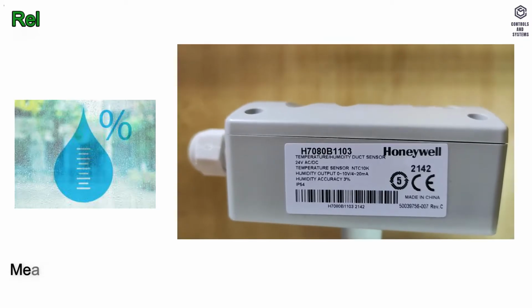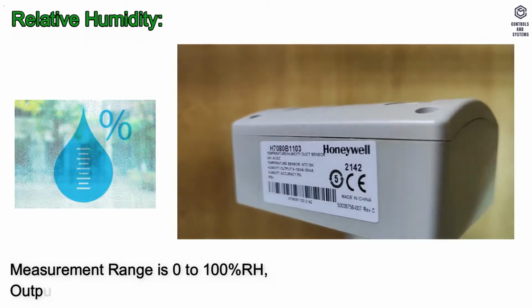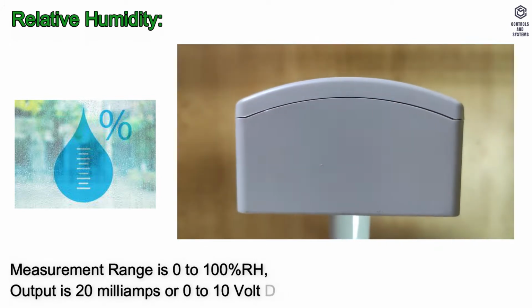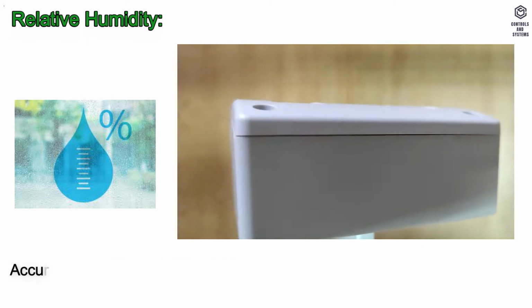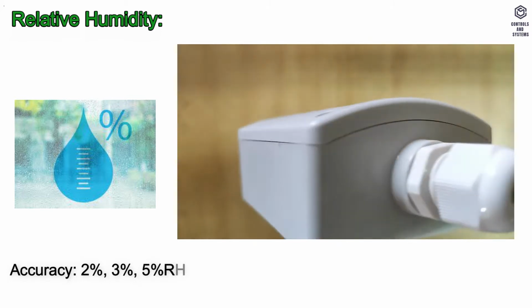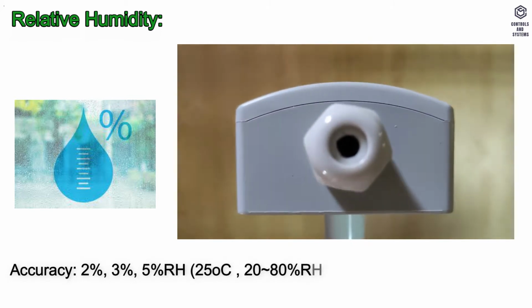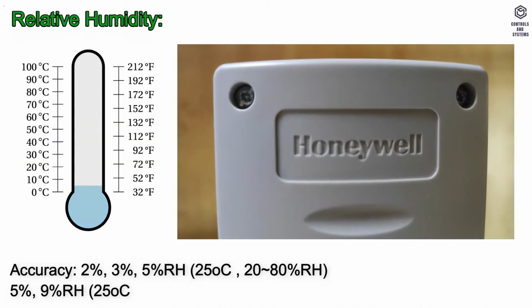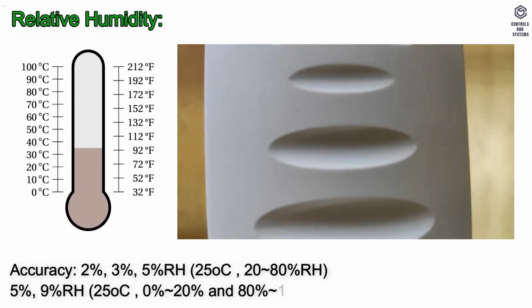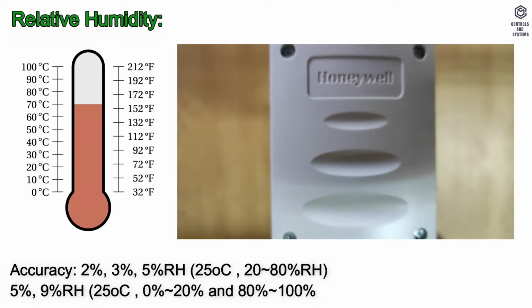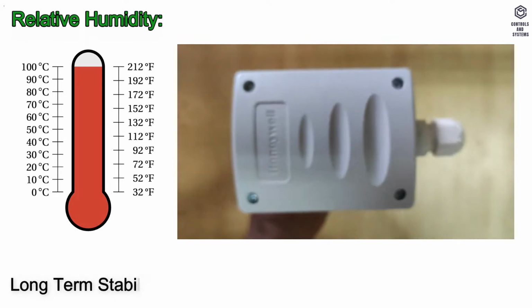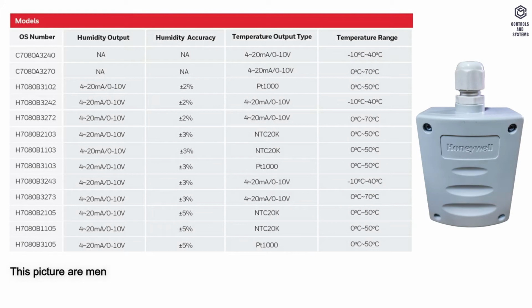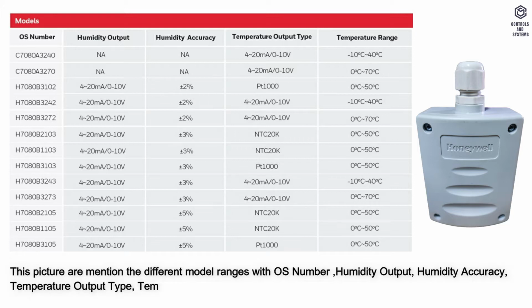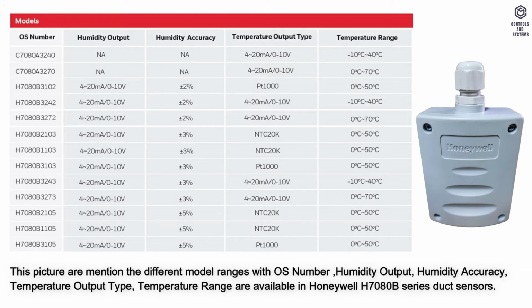Technical specification. Relative humidity measurement range is 0 to 100% RH. Output is 4 to 20 milliamps or 0 to 10 volt DC. Accuracy: 2%, 3%, 5% RH at 25°C for 20 to 80% RH, and 5%, 9% RH at 25°C for 0 to 20% and 80 to 100%. Long-term stability: RH per year. This picture shows the different model ranges with OS number, humidity output, humidity accuracy, temperature output type and temperature range available in the Honeywell H7080B series duct sensors.